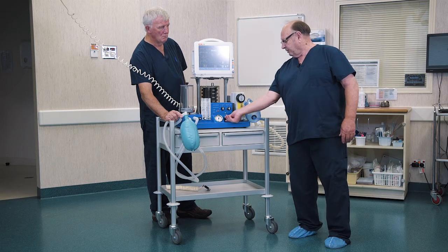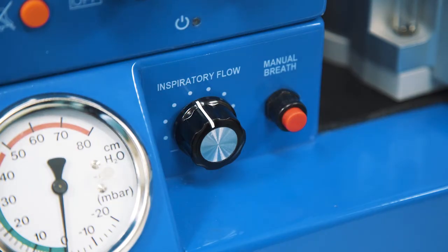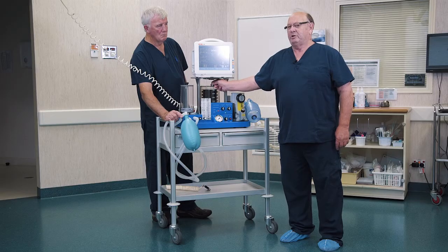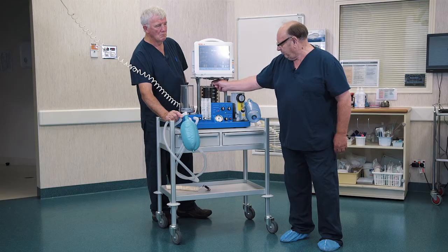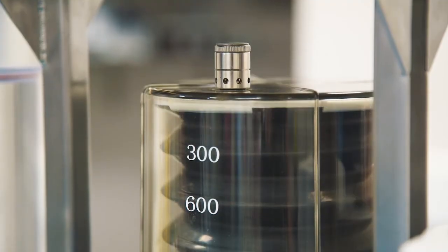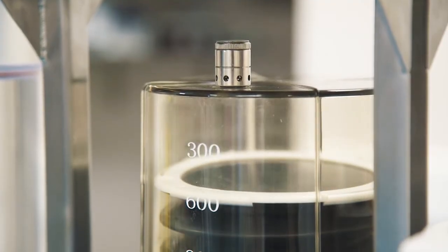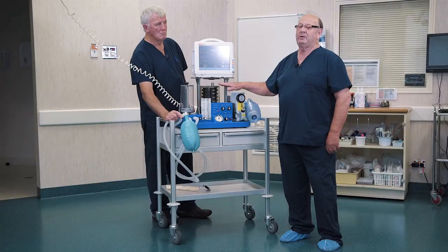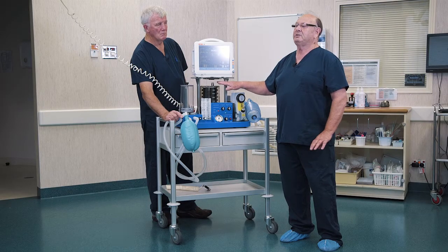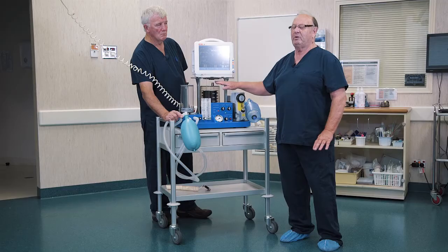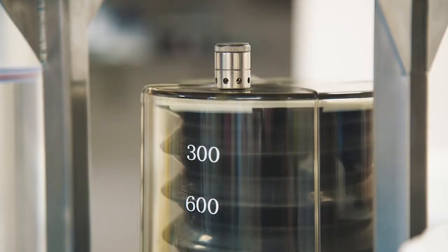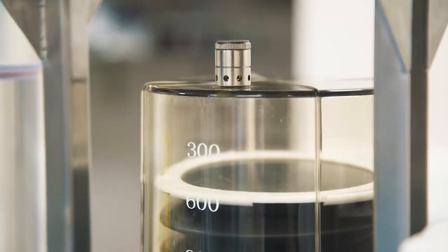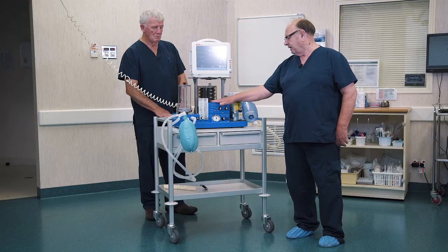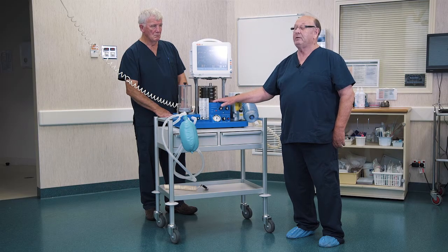We can increase the flow with a flow control here. We can also use pressure control mode by just opening this very simple blow-off valve here. And you can see now that we're pressure limiting at about 20 centimetres of water. It's a very simple idea, and there's no electronics at all involved in this pressure control system. It's completely fail-safe. The alarm system in here also has a negative pressure alarm.